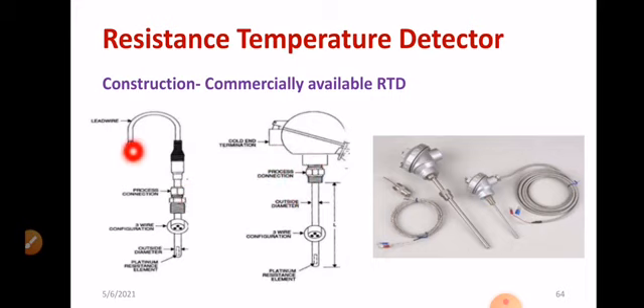So where is the lead wire? Lead wire is mainly used for the calibration. You can see the process connection. Thread is available here. Then 3-wire configuration. I will tell you about 2-wire configuration and 3-wire configuration, and why it is required. And you can see the outside diameter part, then the platinum resistance element. Anyway, you are measuring the resistance of that particular platinum wire, by using any of the resistance measuring techniques.